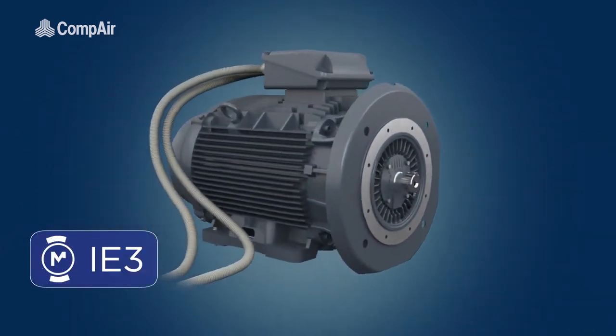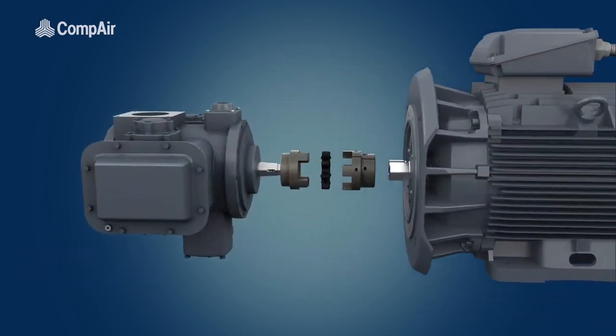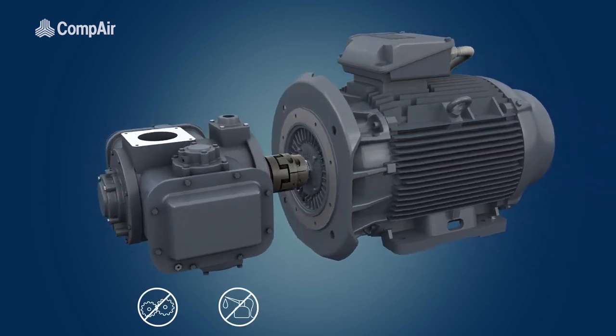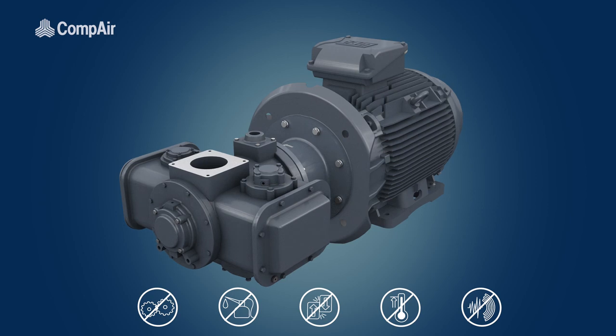It is powered by an energy-efficient IE3 motor with the possibility of a build-to-order upgrade to IE4. This drives the compressor element directly, so there is no requirement for a gearbox, eliminating the need for associated oil lubrication systems, unnecessary friction, heat and noise, which would all equate to wasted energy.